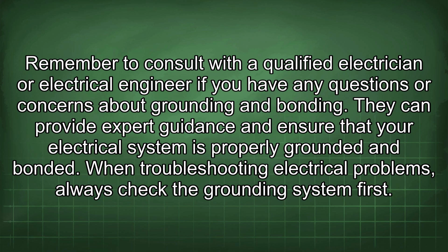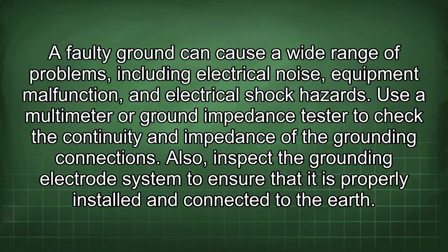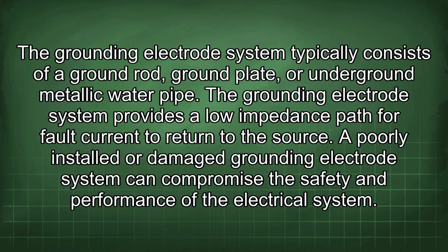When troubleshooting electrical problems, always check the grounding system first. A faulty ground can cause a wide range of problems, including electrical noise, equipment malfunction, and electrical shock hazards. Use a multimeter or ground impedance tester to check the continuity and impedance of the grounding connections. Also, inspect the grounding electrode system to ensure that it is properly installed and connected to the earth. The grounding electrode system typically consists of a ground rod, ground plate, or underground metallic water pipe. The grounding electrode system provides a low impedance path for fault current to return to the source. A poorly installed or damaged grounding electrode system can compromise the safety and performance of the electrical system.